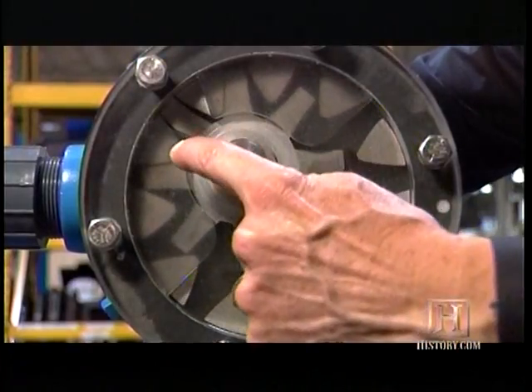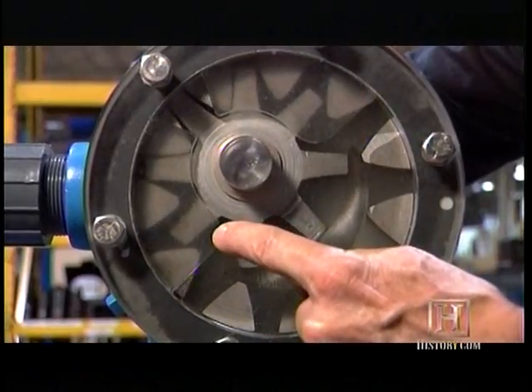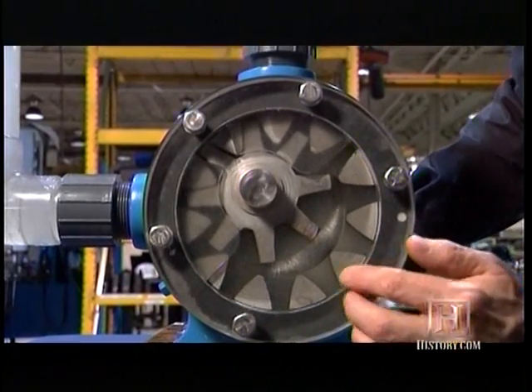As the rotor turns, you can see the gears are coming out of mesh. The liquid is drawn in, comes in between the teeth, and fills the cavities as they come out of mesh. This part here is called a crescent, which seals the liquid in.